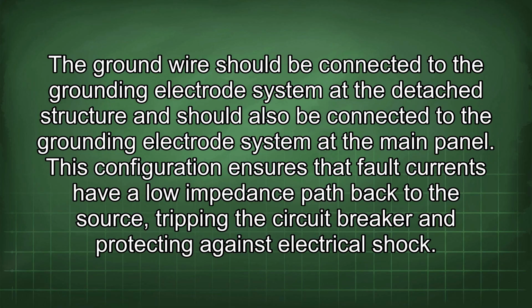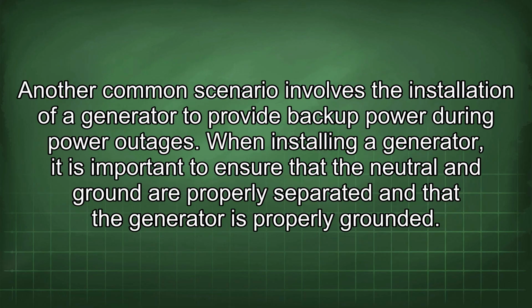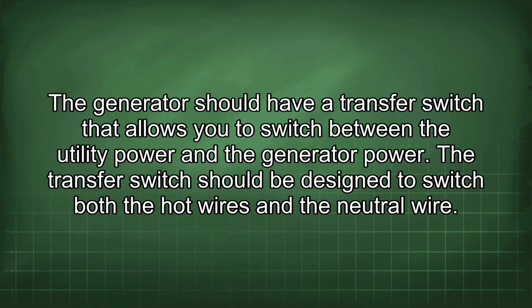protecting against electrical shock. Another common scenario involves the installation of a generator to provide backup power during power outages. When installing a generator, it is important to ensure that the neutral and ground are properly separated and that the generator is properly grounded. The generator should have a transfer switch that allows you to switch between the utility power and the generator power. The transfer switch should be designed to switch both the hot wires and the neutral wire.